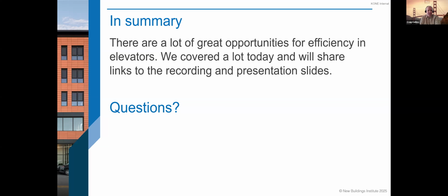The building will generally absorb all of that regen power and the grid will not see it. Now, if you had a condition like we have in our living building where the photovoltaic system is exporting and there's an upper cap on what the utility will allow us to export, and that elevator regen power would tip us over, then you would need some other means of controlling for that to satisfy the utility.